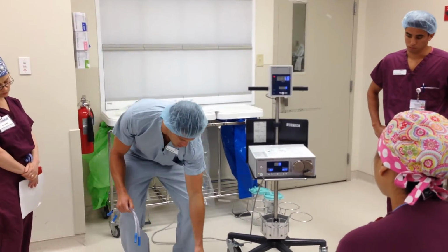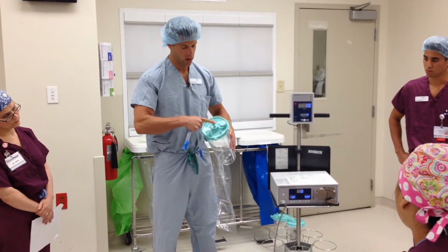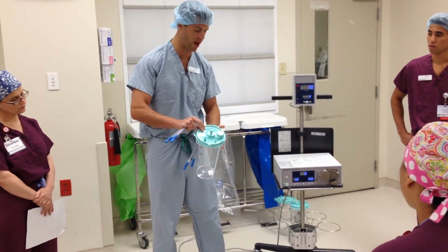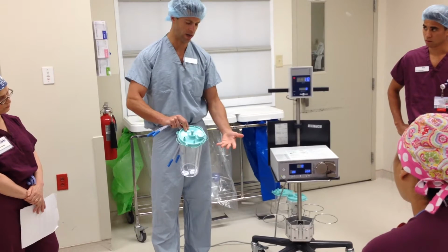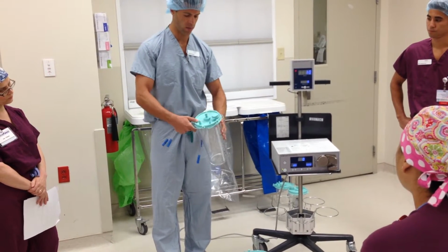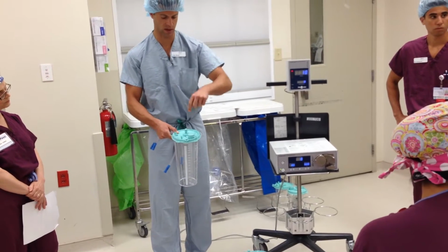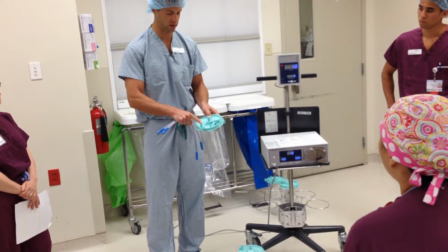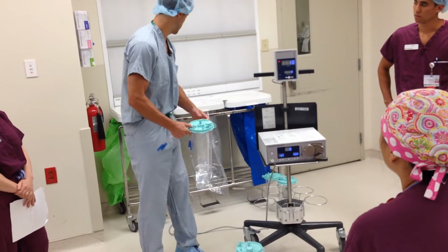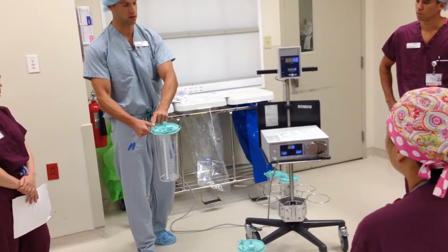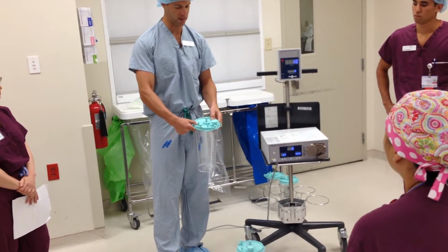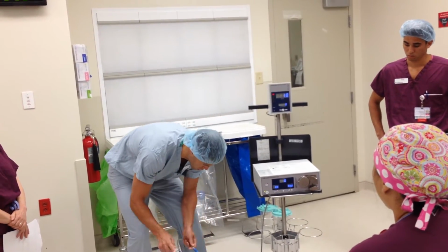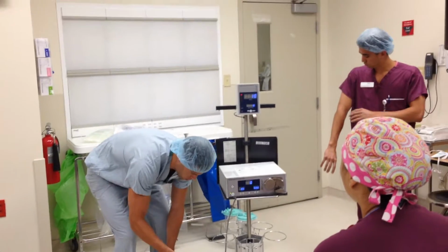So first, we've got the canisters. They're labeled so that this middle portion is always the vacuum. So wherever your suction is coming from, you always want it to be the last canister you're using in your tandem, which I would typically recommend doing at least 2. Your suction will go into the middle, that says vacuum. Then you have a patient one, which is the other big nozzle off the middle, and that's going to be the tubing coming from your patient. So you stick it on that, and then the small little guy is the tandem, so that's where these little tubes will be connected. So I'll just go ahead and tandem this real quick.